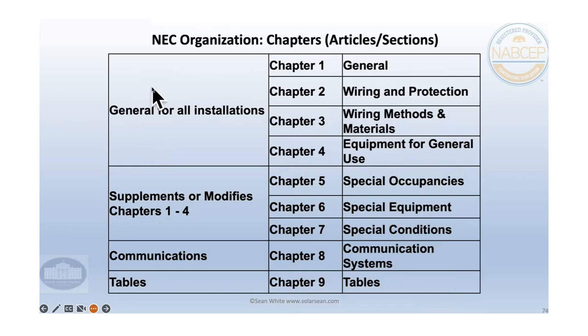And so here we're looking at the way the National Electrical Code is organized. Chapters 1 through 4 are for general installations. That means they apply to everything unless chapters 5 through 7, which mostly we're going to be focusing on, supplement or modify it. And so if we have something different in 706, it supersedes 480 because 480 is in chapter 4. So there's a lot of different reasons why we should be using Article 706 for energy storage and not using Article 480.